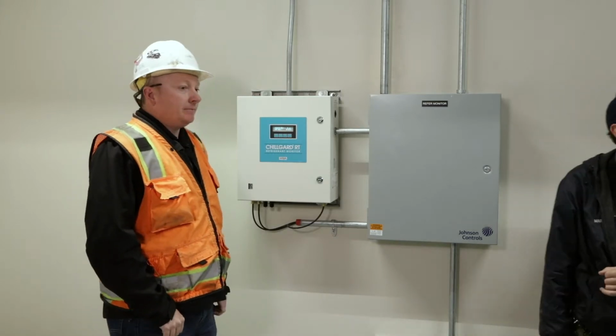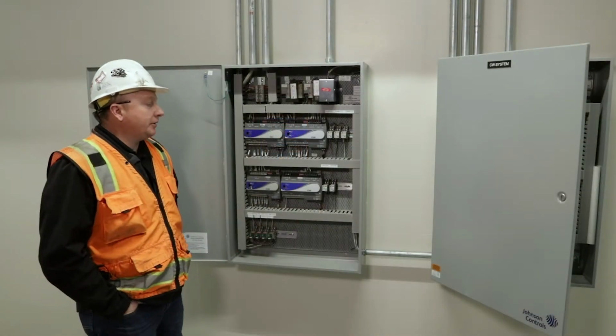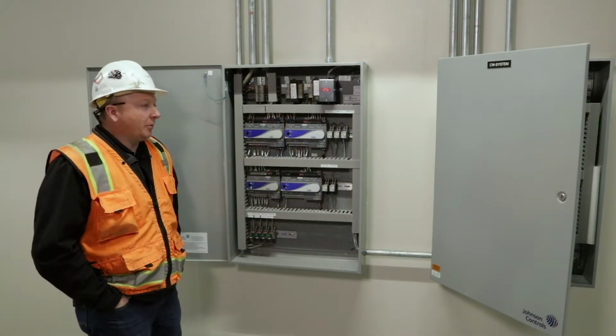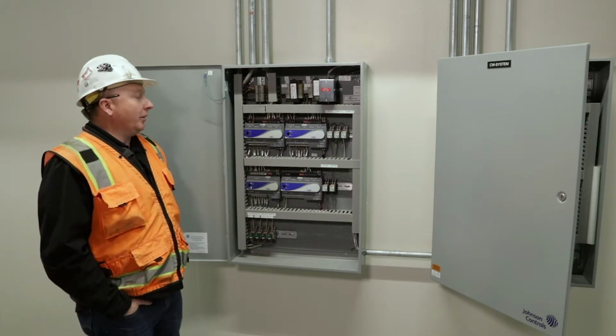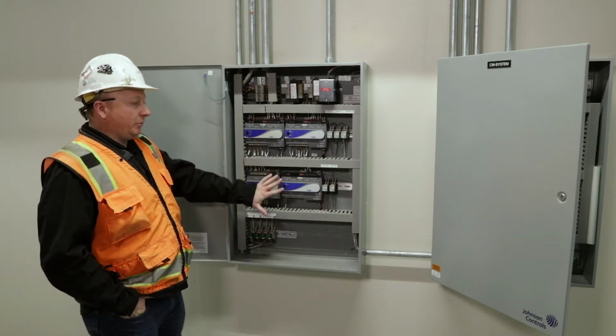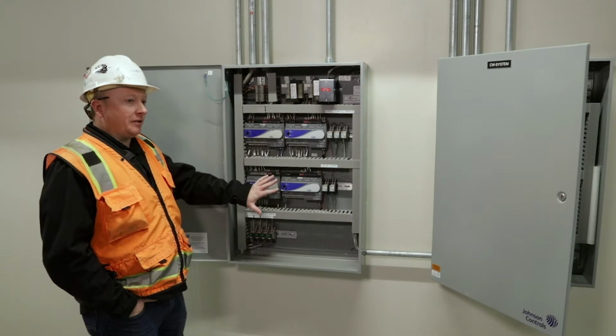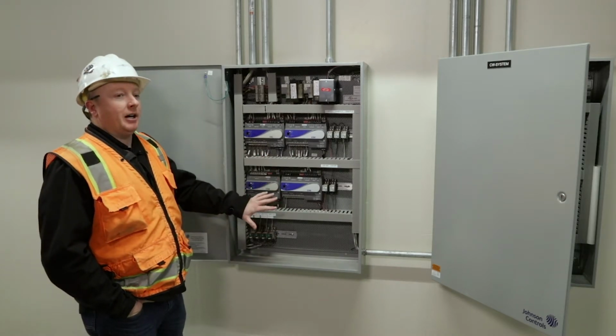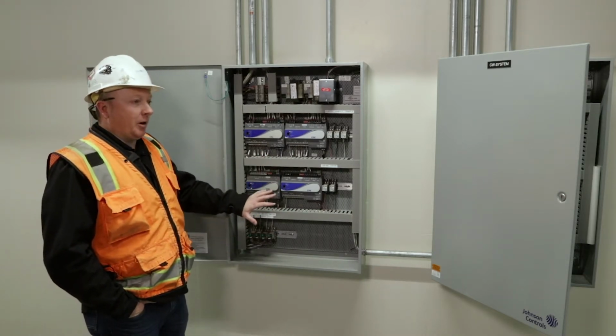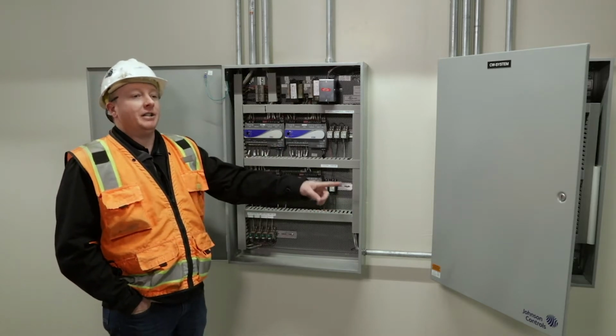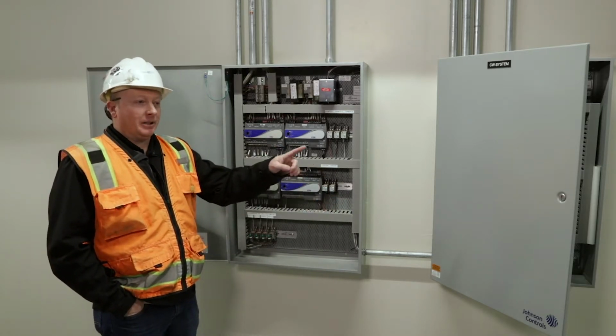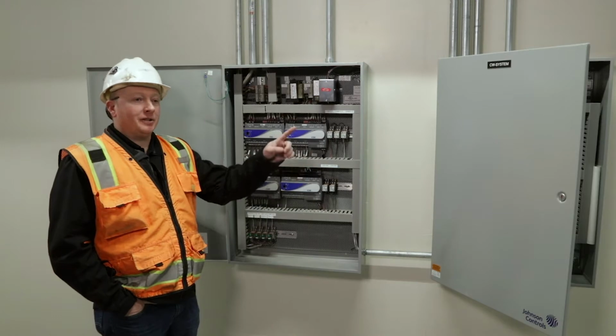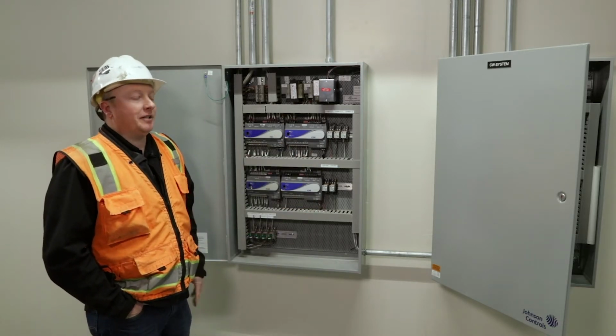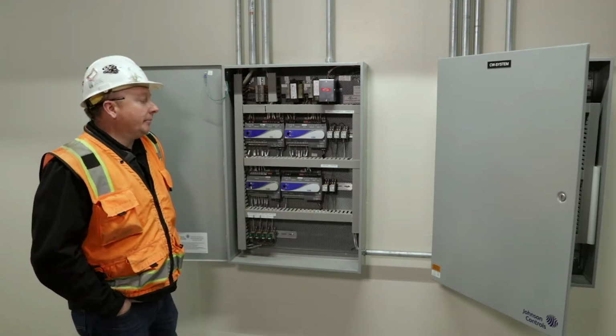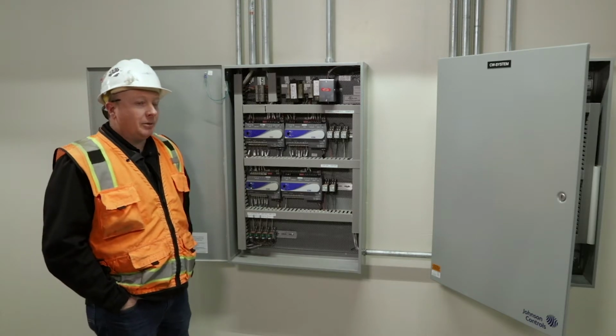Both 134A. All right, guys, so we're going to go over the chill water control panel and the condenser water control panel real quick. So we have 2 separate enclosures. This one does everything for the chill water system. So the chillers, primary chill water pumps, secondary chill water pumps. This panel does the towers, so everything with the cooling tower valves, the VFDs for the fans, all that stuff happens over here. A real quick rundown on the sequence.